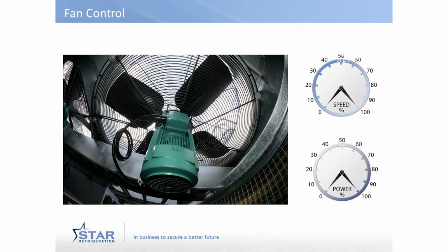Fans and pumps behave differently to compressors, so you need to treat them differently in terms of energy saving. A lot of them are just either running or they're not running. And if you've got a condenser with 10 fans and you can manage to switch off half of them, that's great. You'll save half the energy consumption of the fans. So that's not a bad place to be. However, if you control the speed of the fans, you've got a much stronger lever for improving the efficiency. So a fan which is running on full speed will consume 100% power. That's kind of our benchmark.